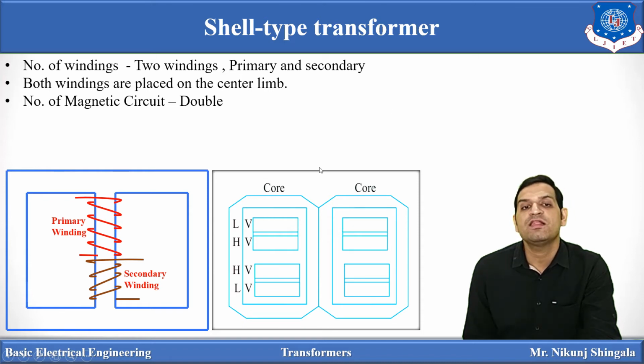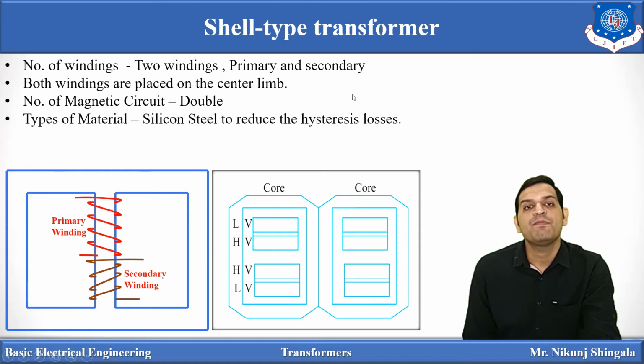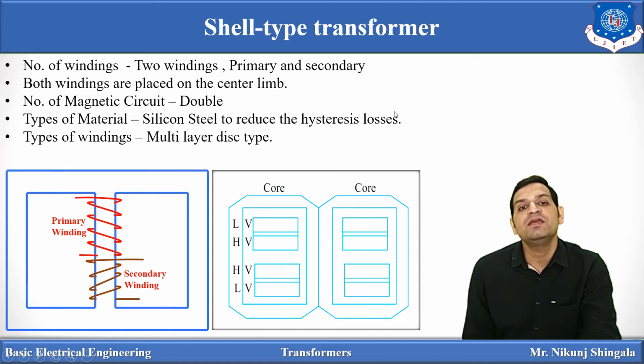Number of magnetic circuits are double in this case. Type of material used to design the core is silicon steel to reduce the hysteresis loss and eddy current losses. Types of winding: multi-layer, disc type or sandwich type of winding is used, primary winding, then secondary, then again primary, then secondary. Now, what about the limbs and yoke?